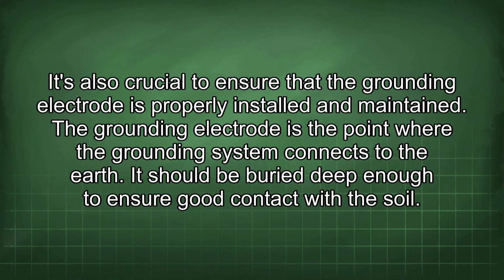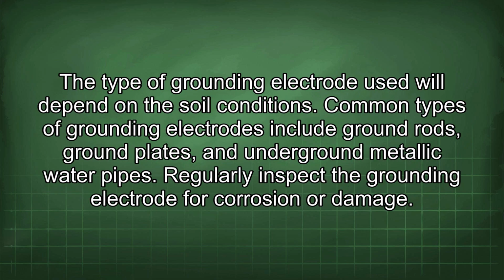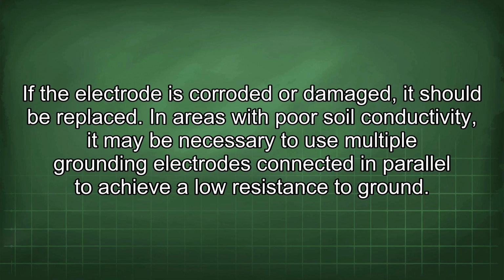It's also crucial to ensure that the grounding electrode is properly installed and maintained. The grounding electrode is the point where the grounding system connects to the earth. It should be buried deep enough to ensure good contact with the soil. The type of grounding electrode used will depend on the soil conditions. Common types of grounding electrodes include ground rods, ground plates, and underground metallic water pipes. Regularly inspect the grounding electrode for corrosion or damage. If the electrode is corroded or damaged, it should be replaced.